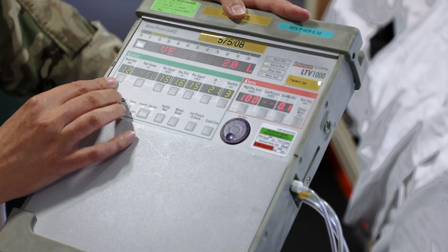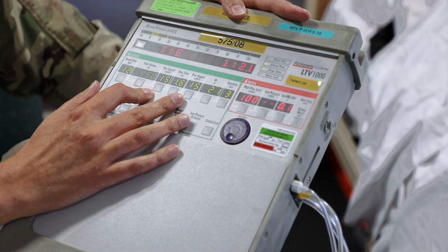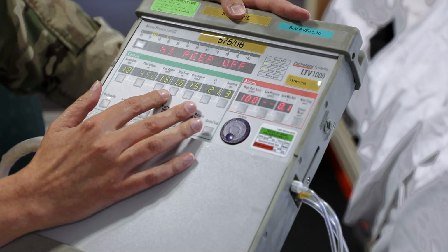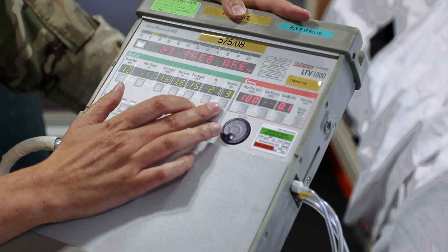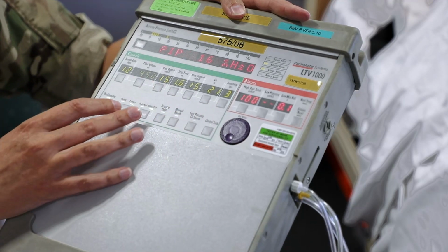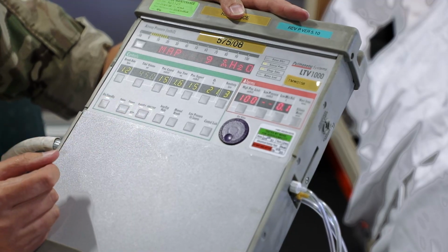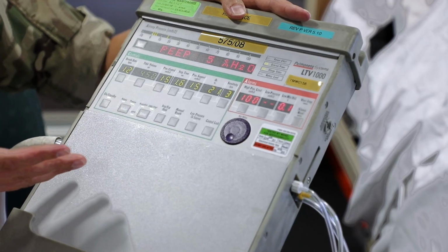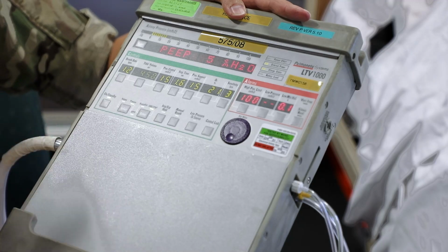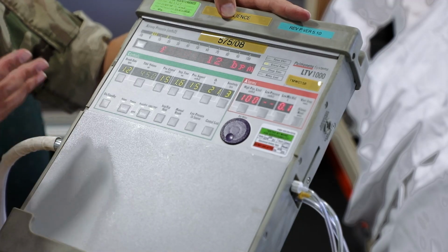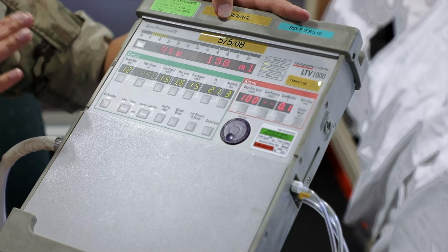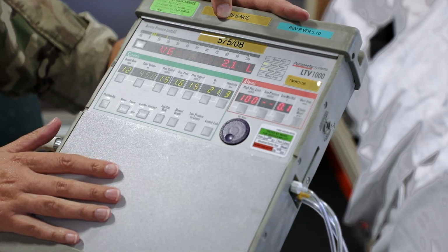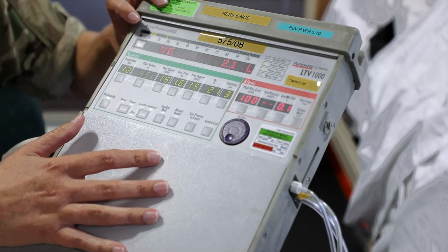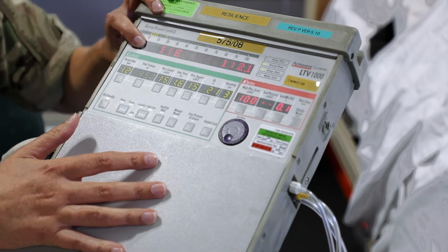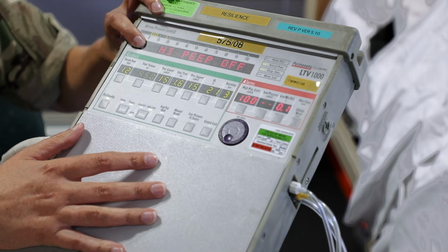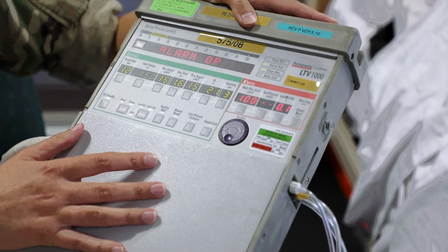So you'll see here I have a respiratory rate of 12, the pressure control and support at 15, an inspired time of 1.6 and a sensitivity set at 3, and I am in a pressure SIMV mode. The reason for having it standardized is just that every time a transducer check is complete, it's done with exactly the same settings. So to get into that transducer menu, I'm going to press and hold the select button, which takes me into our menus.